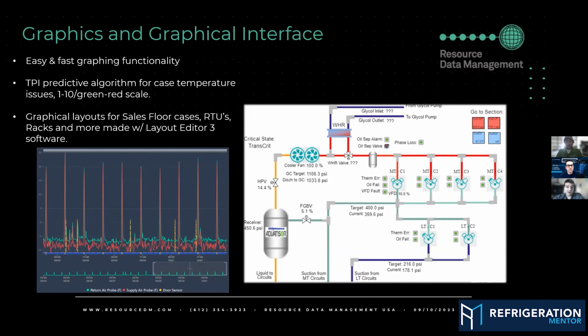Graphing, I like graphing on this system. It's really fast. You can pull a lot of data, like pulling a 48-hour graph snippet is really quick. It's like seconds. If you want to pull a week, 10 or 15 seconds. The data manager stores, I think, up past 5 years of data. So you can actually look way back in your system to see what happened last year during this time versus what's happening now.